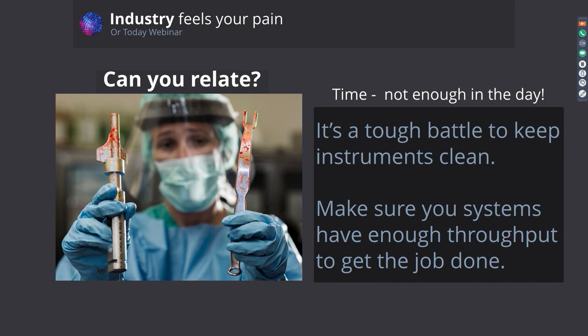Make sure your systems, particularly your ultrasonic machines, have enough throughput to get the job done and keep up with the pace as well. And if you're looking for an ultrasonic system, consider the options and decide what works well for your department. It doesn't have to be a bonded transducer machine. It can be a machine with a titanium rod transducer, or TRT, or rod transducer. It can be a bonded transducer. They all do effective cleaning.